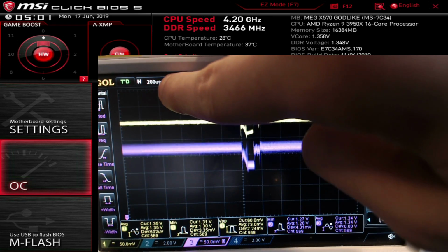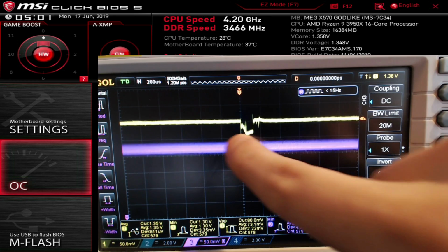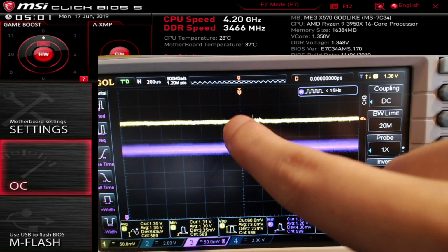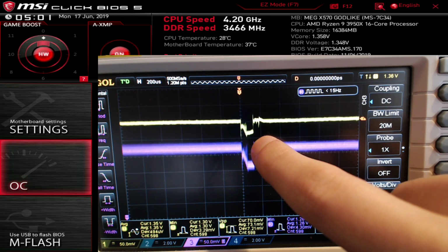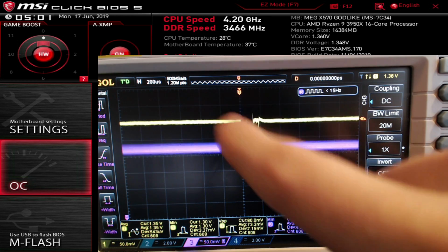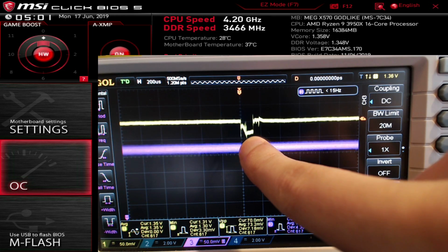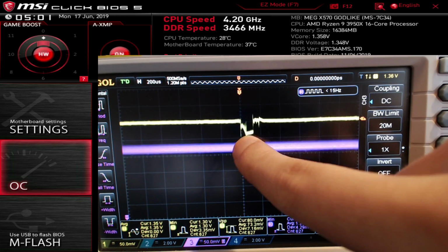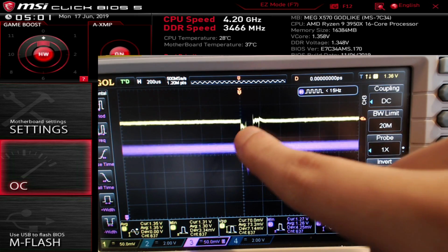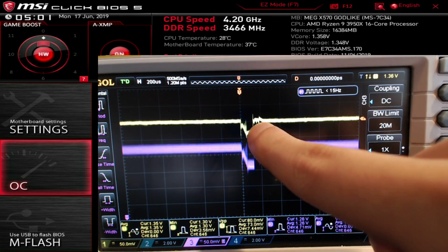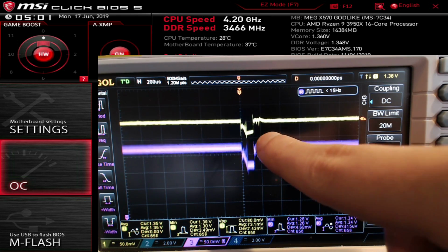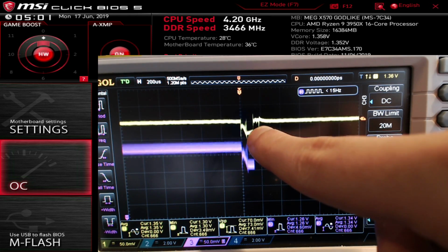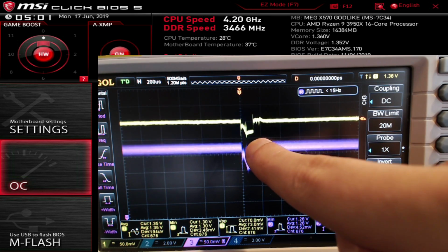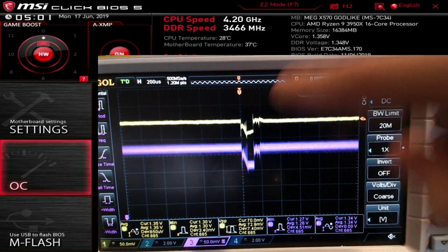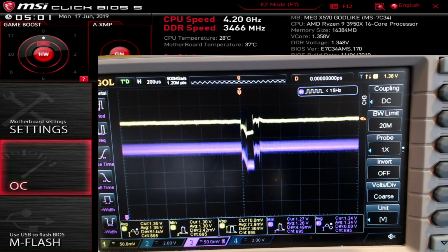Right now we're at 200 microseconds per division, so this entire event is 200 microseconds long. The fastest update rate I've seen on most monitoring software is about 1 millisecond, so your Windows monitoring software is never going to see anything like this. It's never going to pick up on a 200 microsecond event. Actually, it's not even really 200 microseconds, since it's back up to 1.35 volts before the end of that division, but you get the idea — it's a sub-200-microsecond event. Your software will never pick up on that, but it is going to affect your stability.